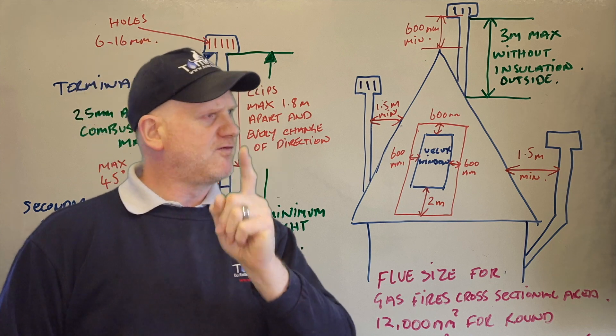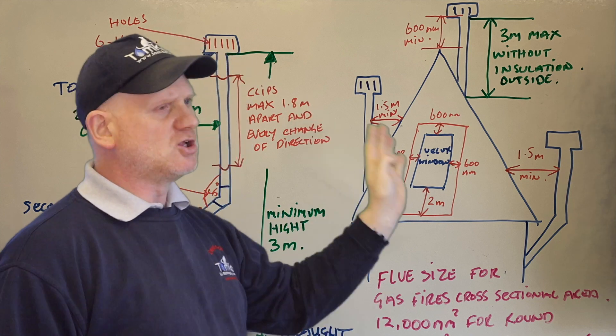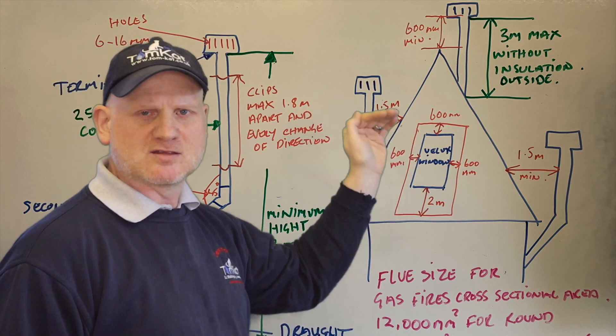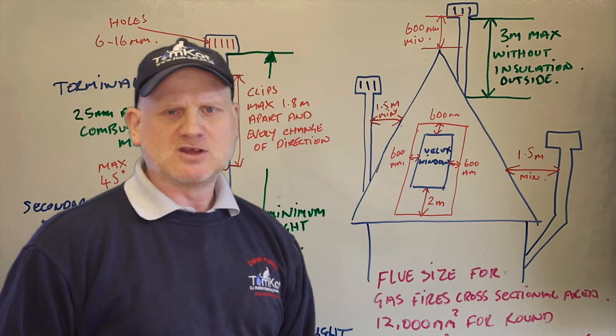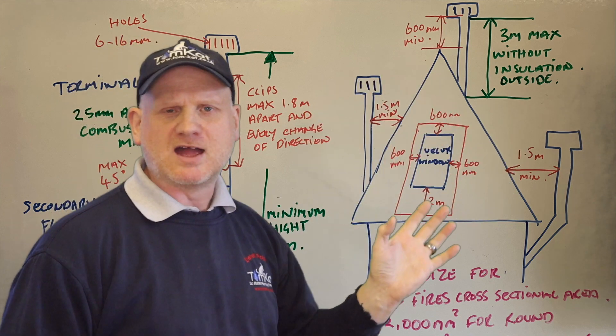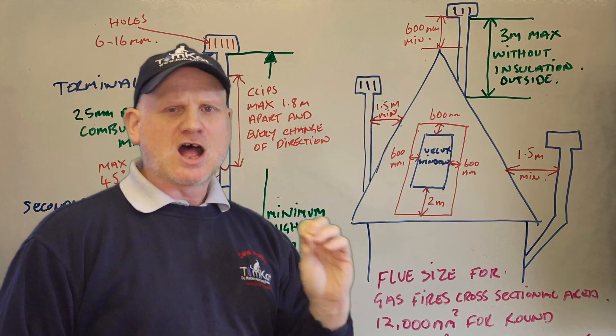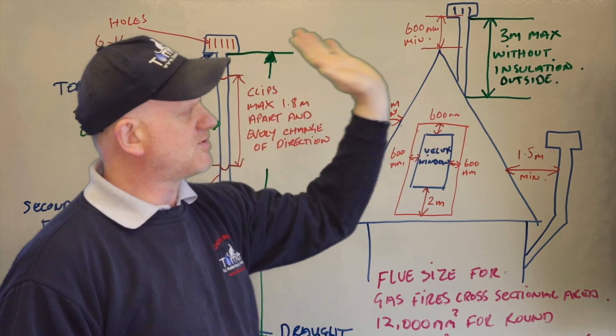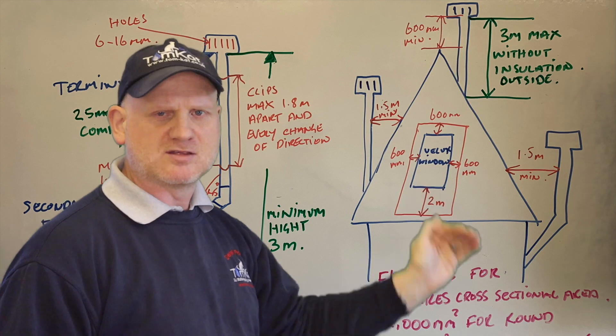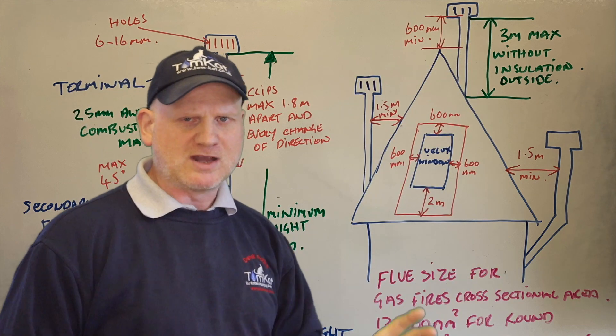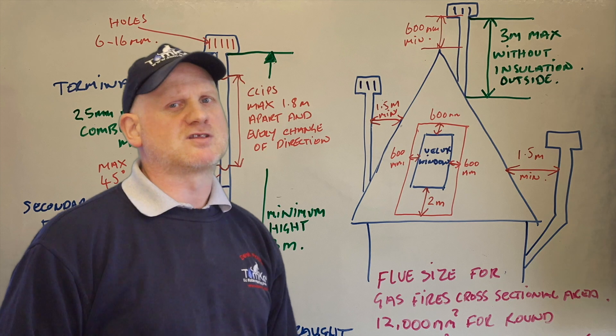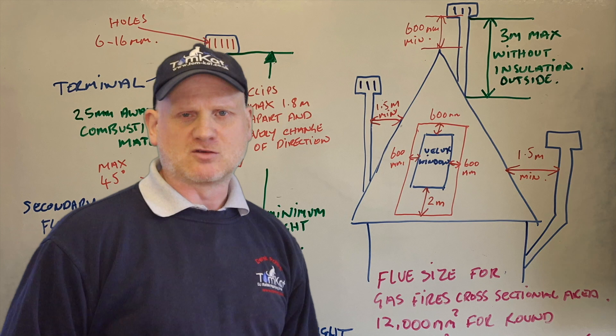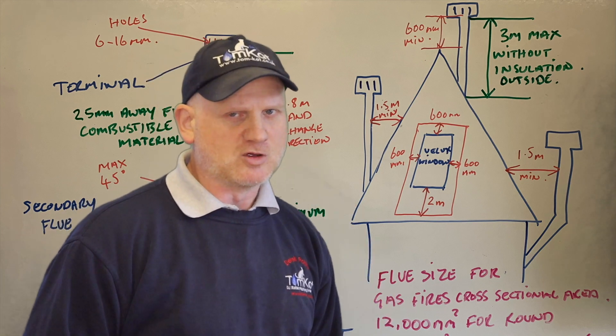For Velux windows — and these measurements also apply to room sealed appliances — at the bottom of the window you need two meters clear of any flue. The shaded exclusion zone around the window is: 600mm to each side, 600mm at the top, and two meters down at the bottom. You're not allowed to put the flue system within that rectangle around the window.